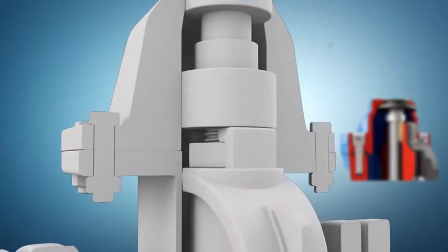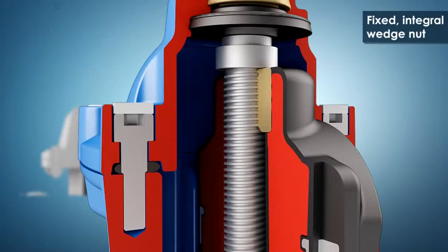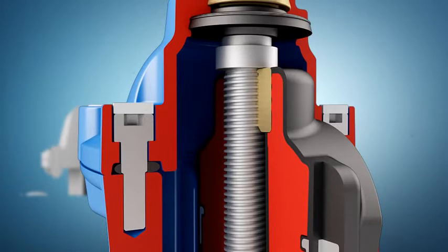Most gate valves are designed with a loose wedge nut placed in a bayonet socket in the wedge, where it is difficult to obtain sufficient rubber vulcanization. The loose wedge vibrates when influenced by the flow, which leads to abrasion of the thin rubber layer. AVK's fixed integral wedge nut design prevents vibration and consequently also internal corrosion, malfunction, and water hammer. It is sealed at the top and bottom with rubber to prevent corrosion and is made of de-zincification resistant brass with lubricating abilities.